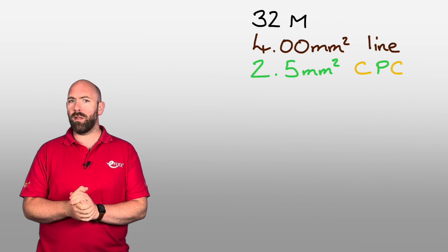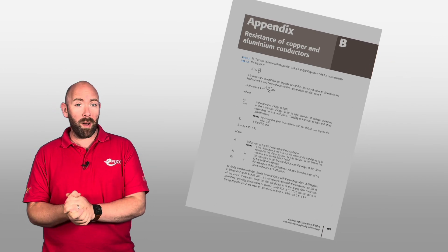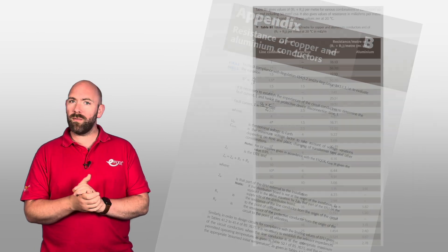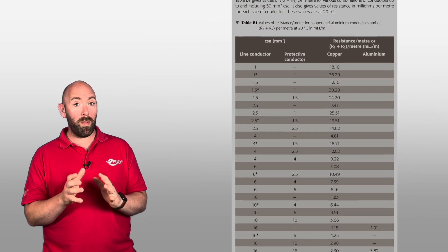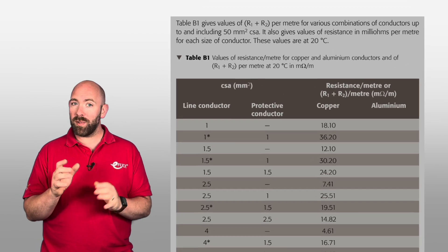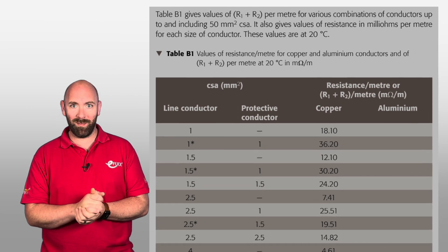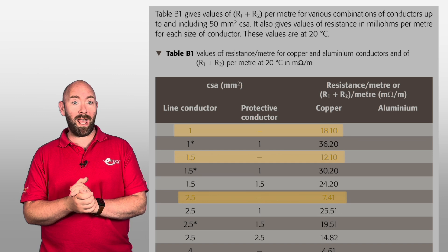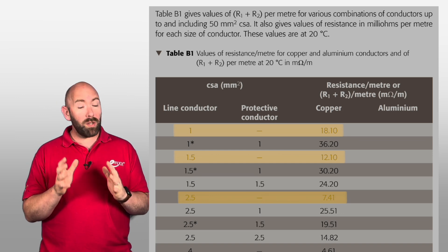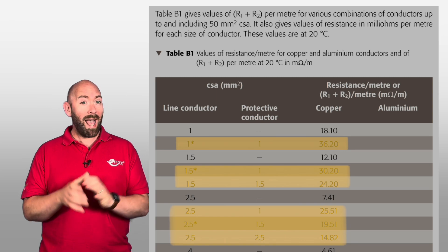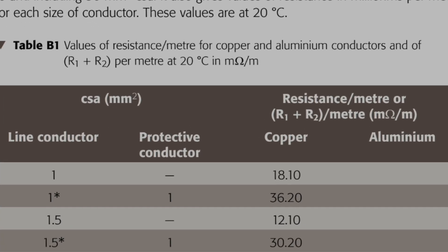Appendix B of Guidance Note 3 outlines the resistance of copper and aluminium conductors. Table B1 shows the values of resistance per metre for copper and aluminium conductors at 20 degrees Celsius. Using the table we can see the resistance of cable by cross-sectional area per metre. It also shows us the combined resistance of the line and protective conductor, as well as the line conductor by itself, and the values given are in milliohms per metre.